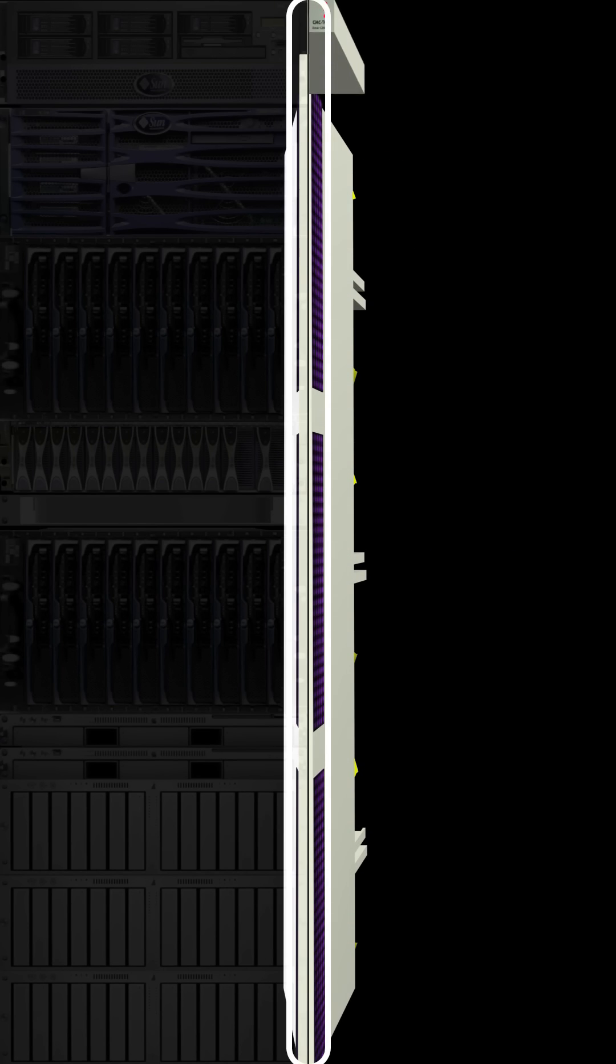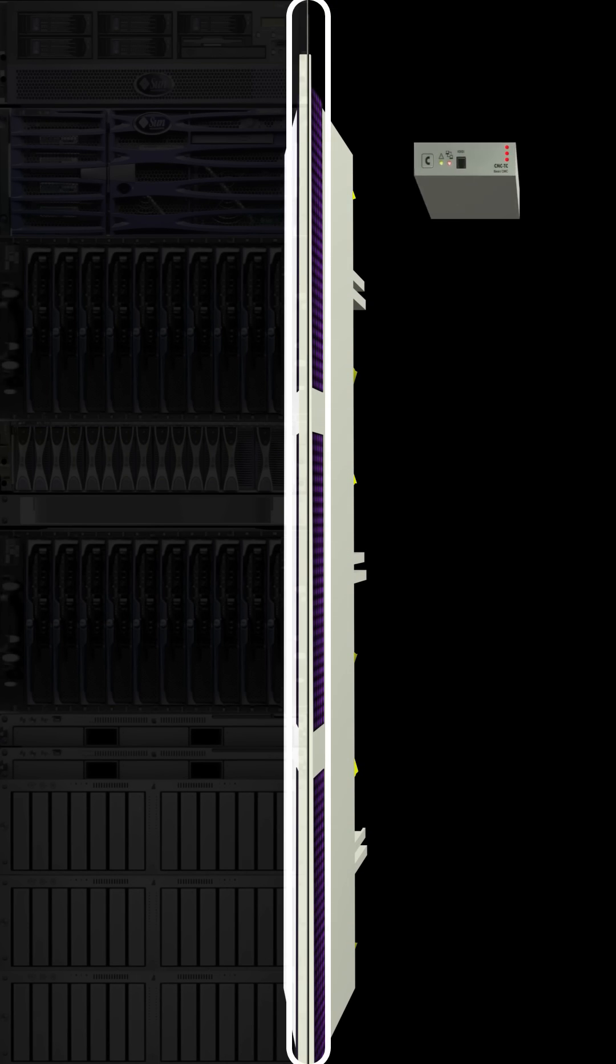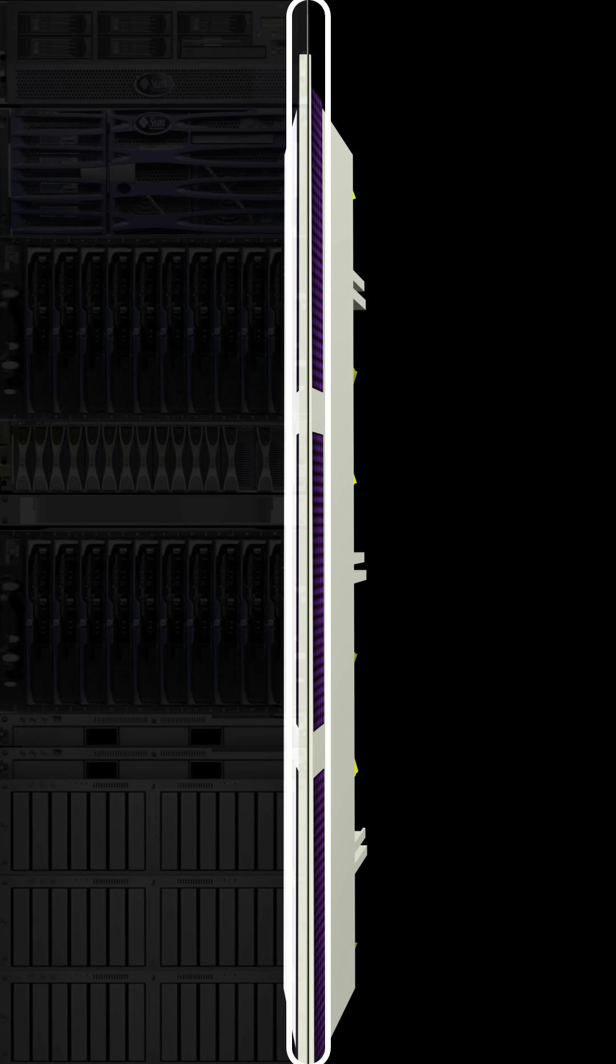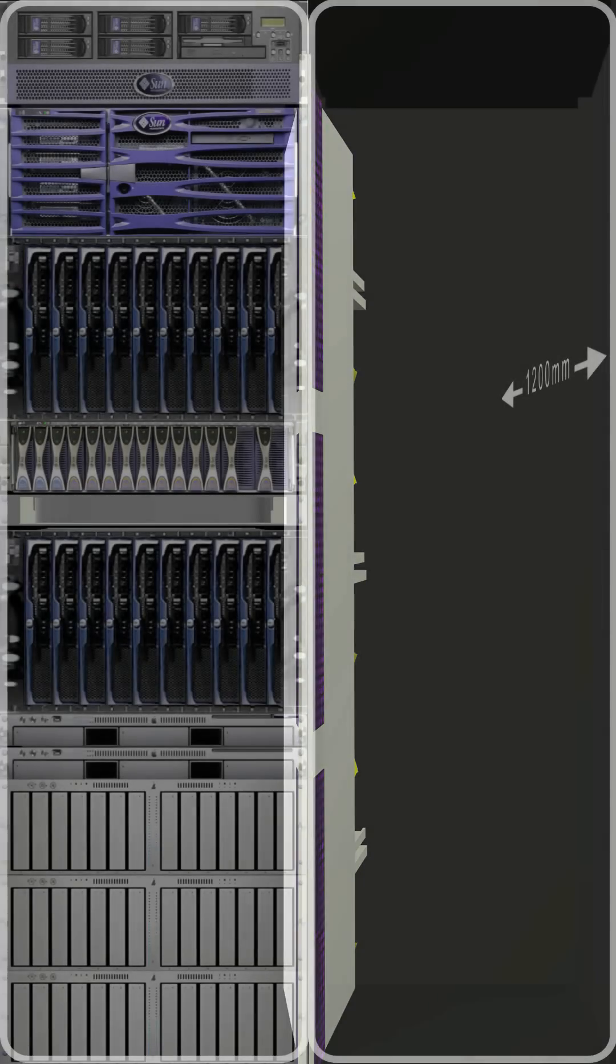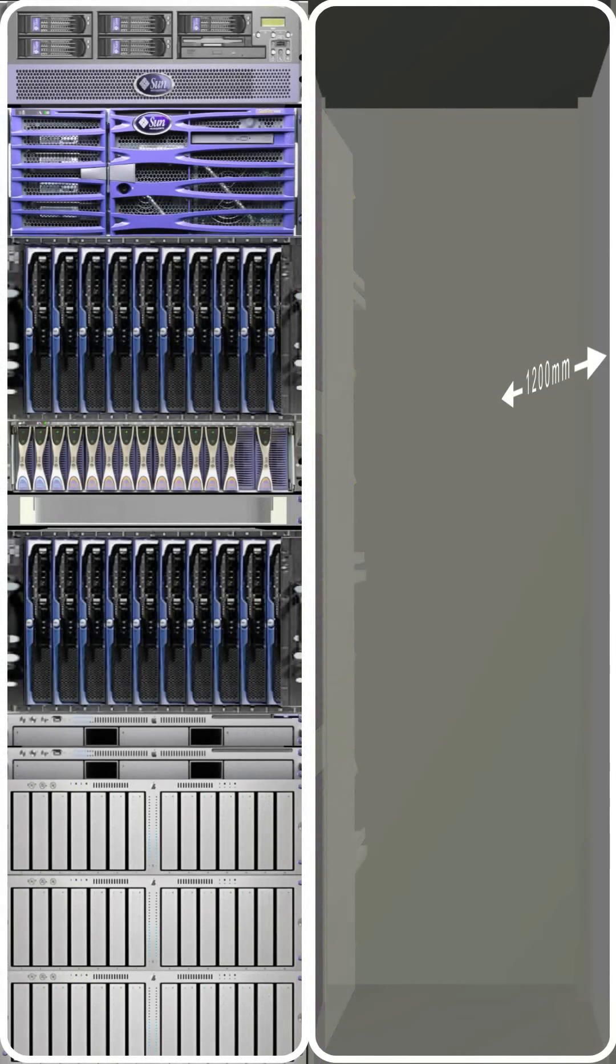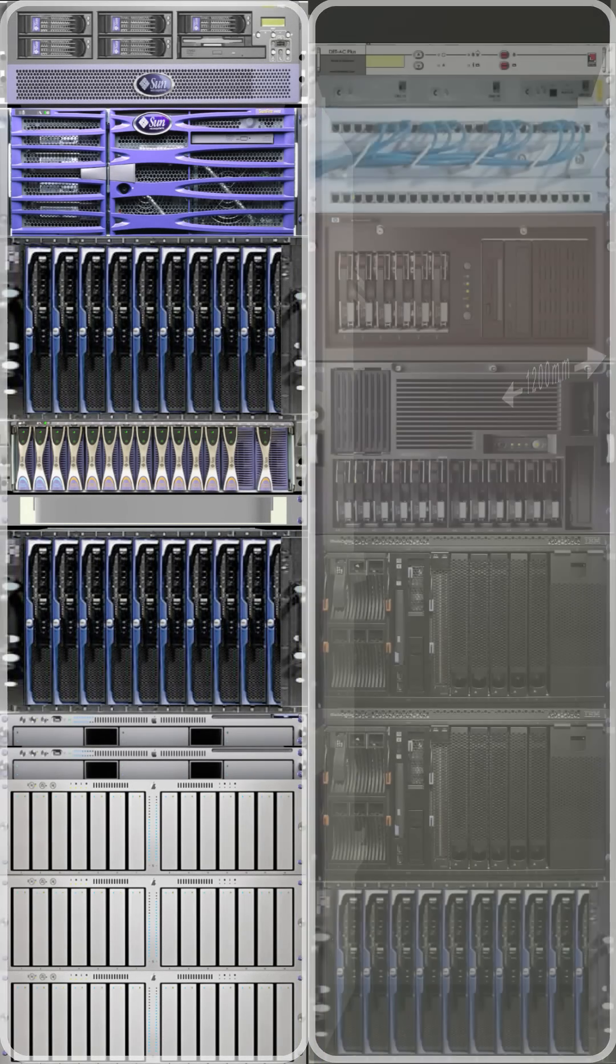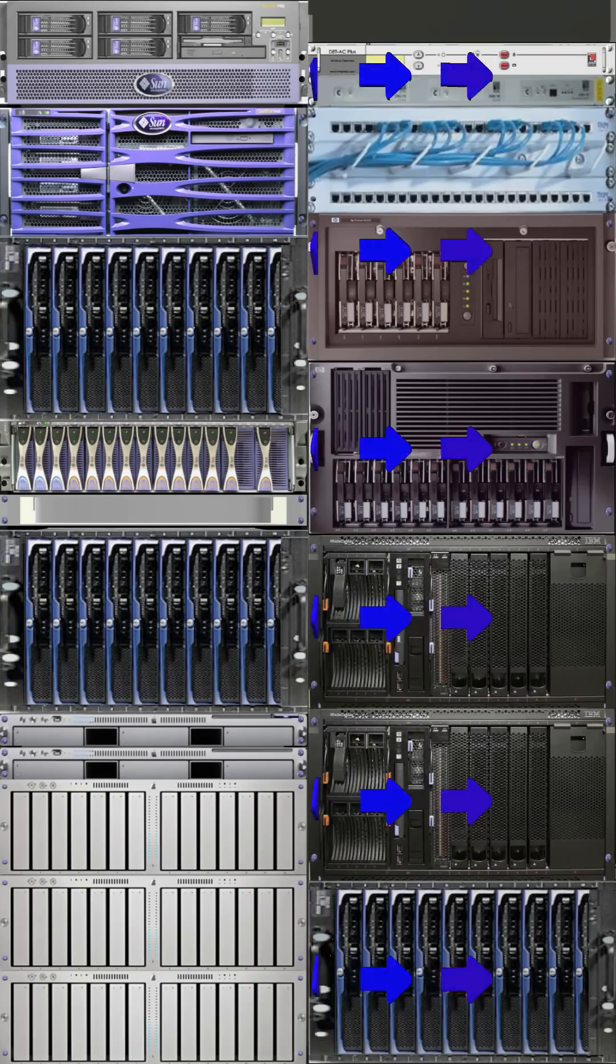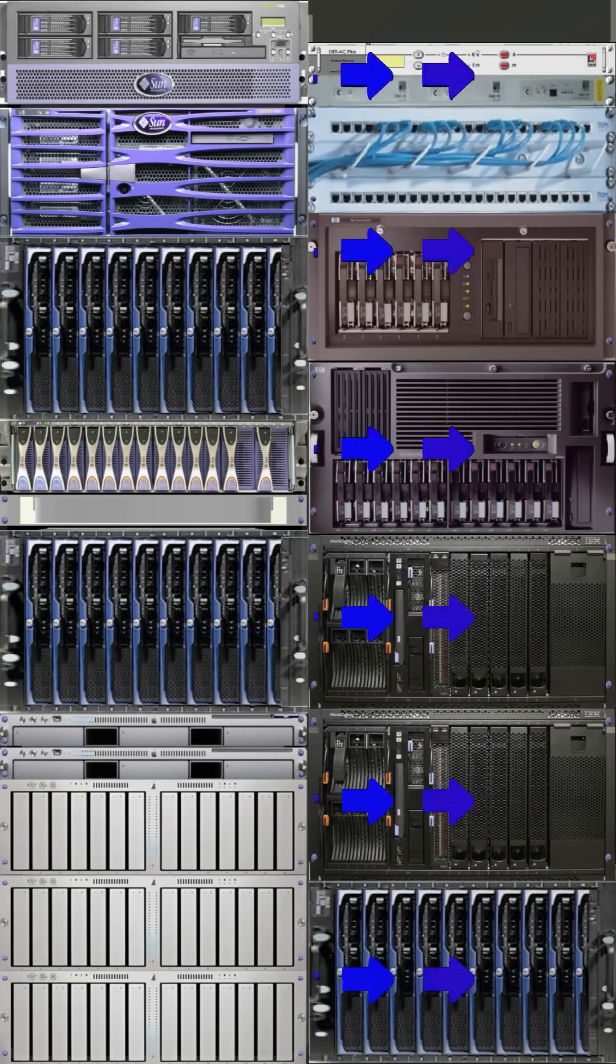Intelligent modules monitor the fans and the flow rates and are displayed on a touch-sensitive LCD screen on the front of the LCP Plus. The LCP Plus is connected to a standard 1200mm deep enclosure and pulls the hot air from the server exhaust and cools the air via the heat exchanger.